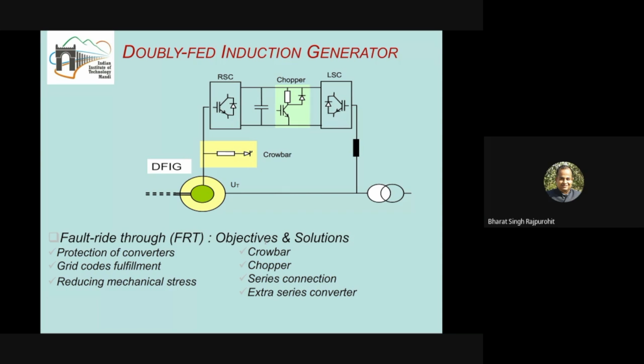We are also able to see that by utilizing this rotor side converter, if an extra amount of reactive power is injected into the air gap, that will be able to transfer from this air gap to the stator circuit and then finally to the grid. So this is how the rotor side converter can be controlled and utilized to feed the reactive power requirement of the DFIG as well as the reactive power requirement from the grid. So this is how the overall DFIG system will be able to operate to meet the fault condition as well as the active and reactive power conditions.